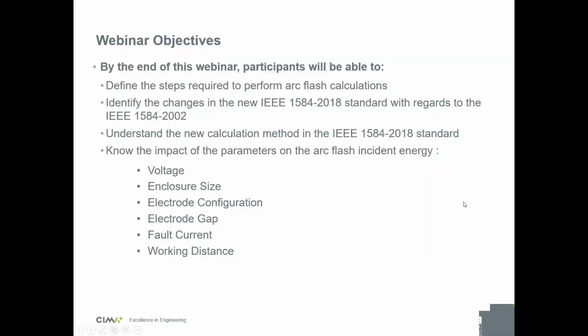So the objectives for this webinar today. I hope that by the end of this webinar, you should be able to know what steps are required to perform arc flash calculations. So how the parameters are used in the equations. Know the differences between the old 2002 version and the new 2018 version. And also know a bit the impact of the parameters on the incident energy. So, for example, the voltage, how it impacts the energy, how the enclosure size, so width, depth, and height of the enclosure, how it affects the energy, the electrode configuration, the electrode gap, which is the distance between the phases, the fault current, and the working distance.